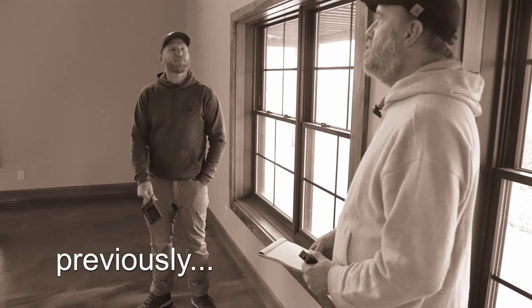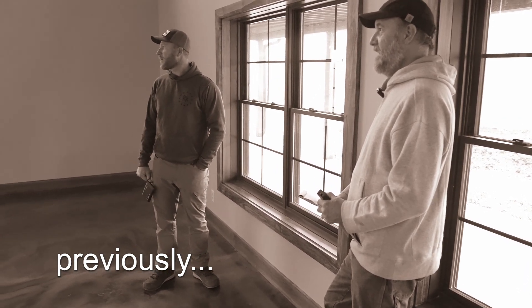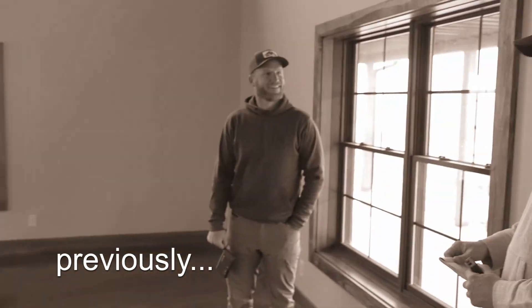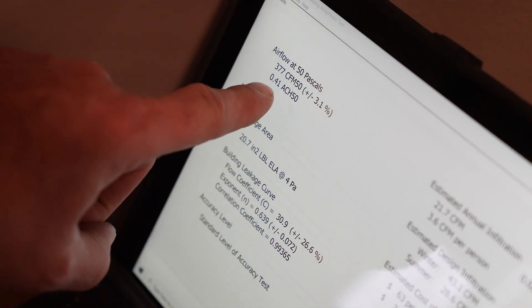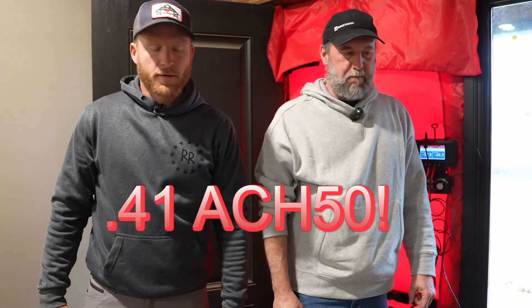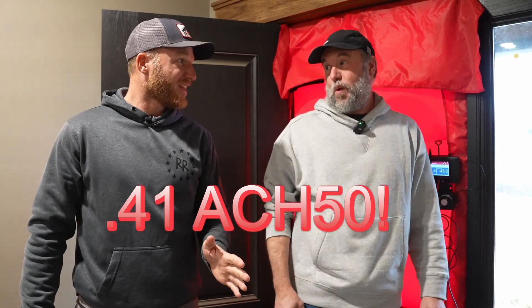What would you expect this to hit based on what you've seen? I would expect you to be in that neighborhood of 1. Dan guesses 1.4. I'll go 0.9. We're at 400 CFM and you're tight — you're really tight. We're basically at minus 50 Pascals. You're under 400 CFM. We're both way off on our guess — that's a good thing, you're way lower. Maybe too tight? You've got an air exchanger, so you can't be too tight. You're good.